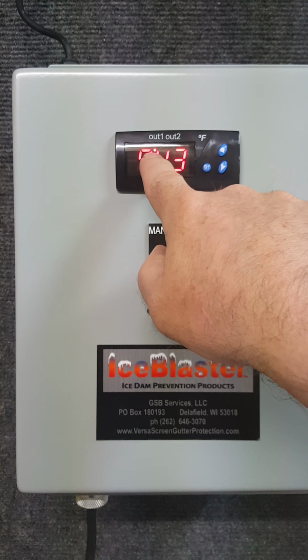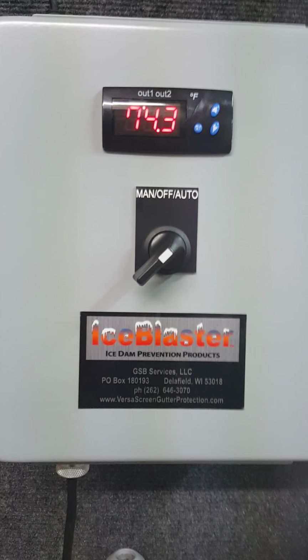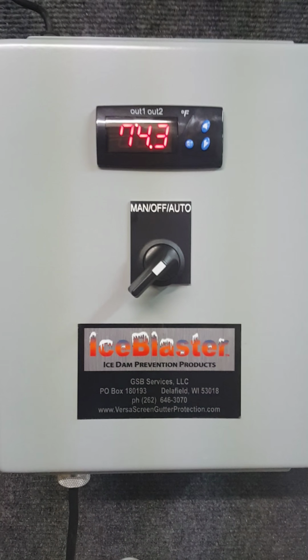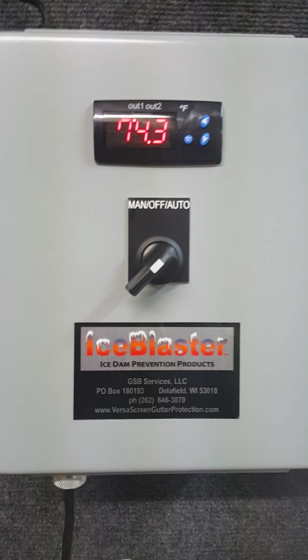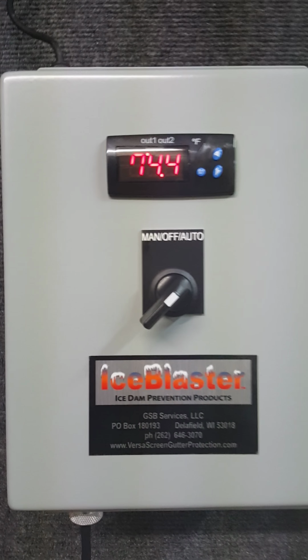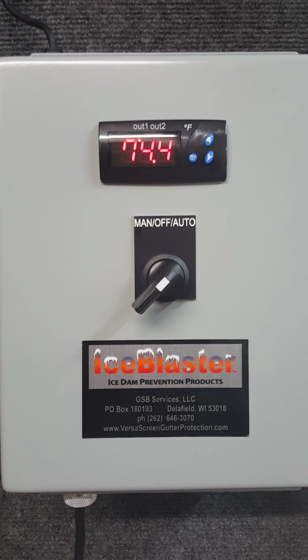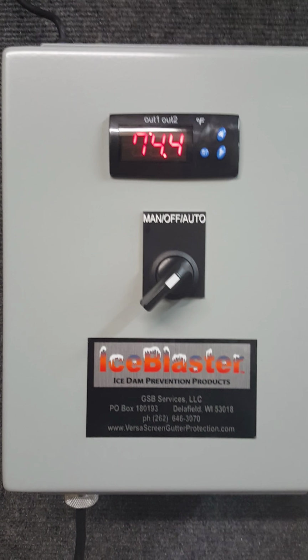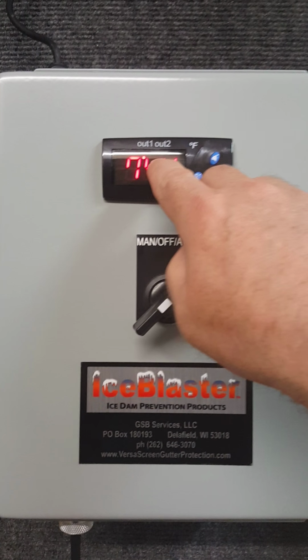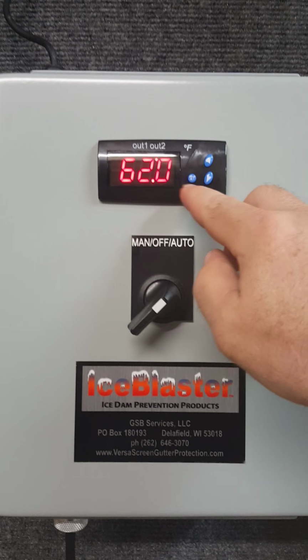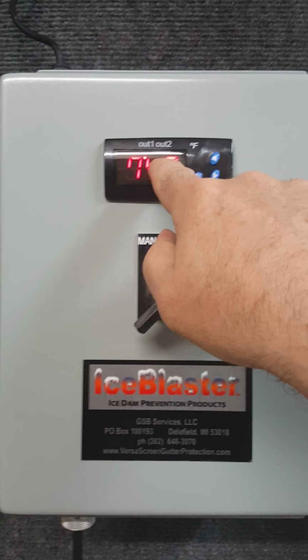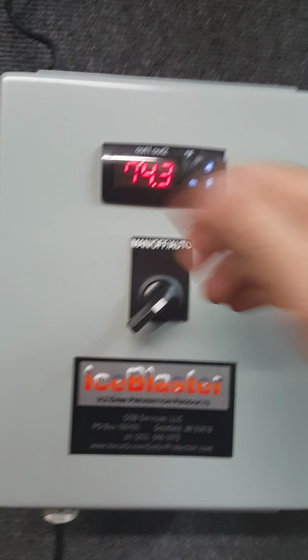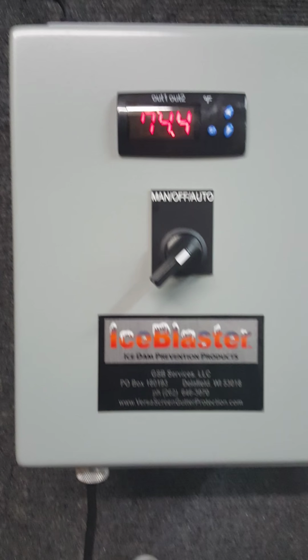The light is on under Out 1. That means it's closed the switch, the contactor that's inside there, and it's allowing power to go to the heat cables. So it's energized in effect. When the dot would appear under Out 2, let's say the temperature fell below that second point that we set, let's say the temperature fell below 62, then we would see an additional dot under Out 2 indicating it was below that low temp cutout.